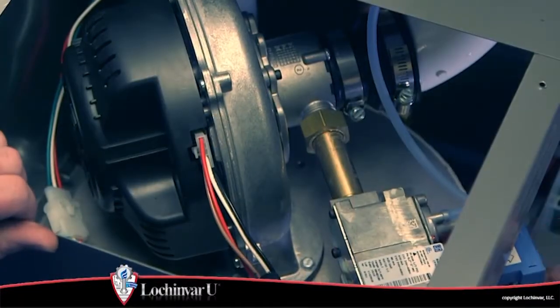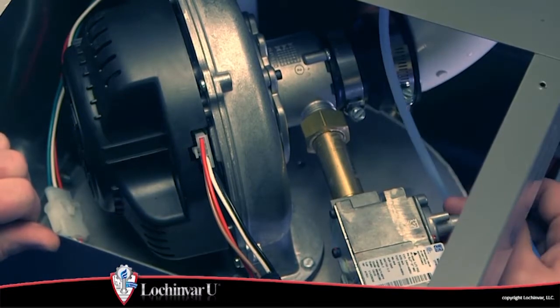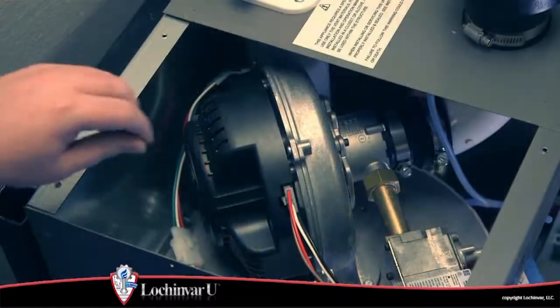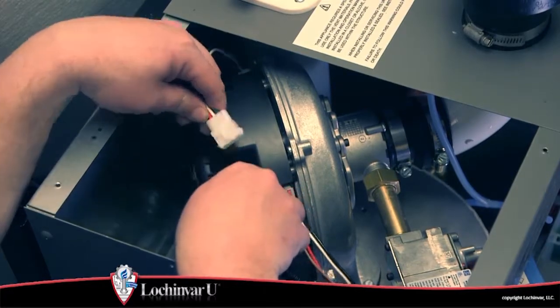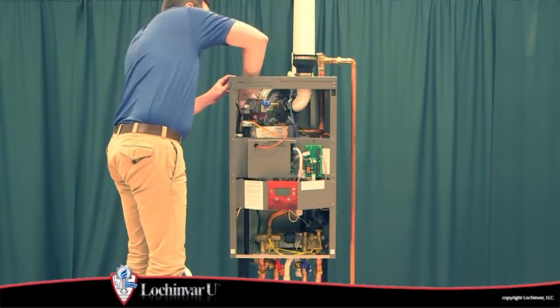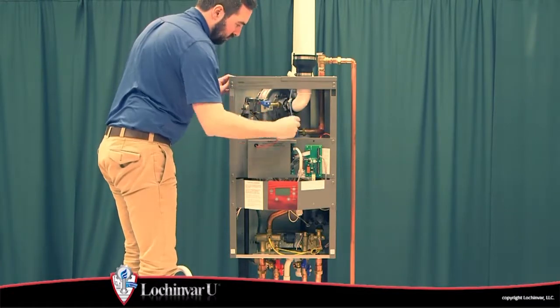Locate and disconnect the gas valve wiring harness and reference hose from the gas valve. Then locate and disconnect the two wiring harness connections to the fan assembly, and locate and remove the wiring from the spark igniter and ground terminal.